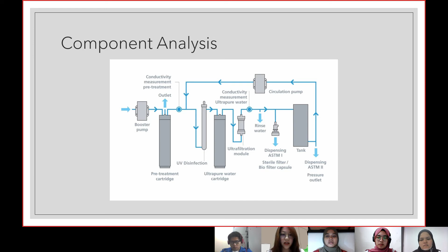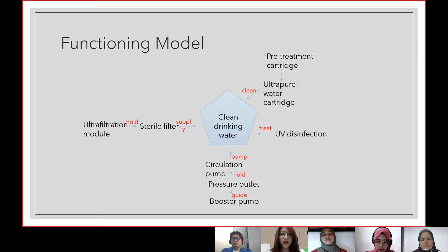Next. For the functioning model, the clean drinking water is treated by UV disinfection and cleaned by the pre-treatment cartridge and ultra pure water cartridge, and is supplied by the ultrafiltration module which holds the sterile filter and is pumped by the circulation pump, which is held by the pressure outlet and guided by the booster pump.